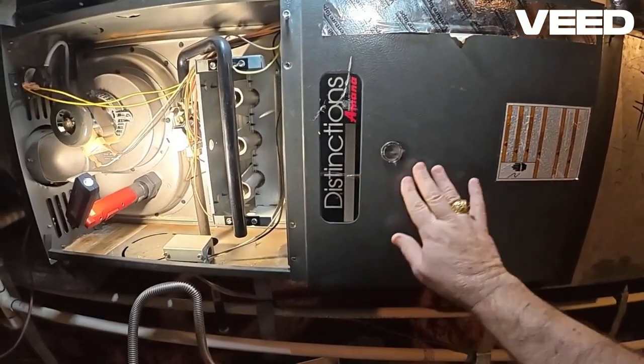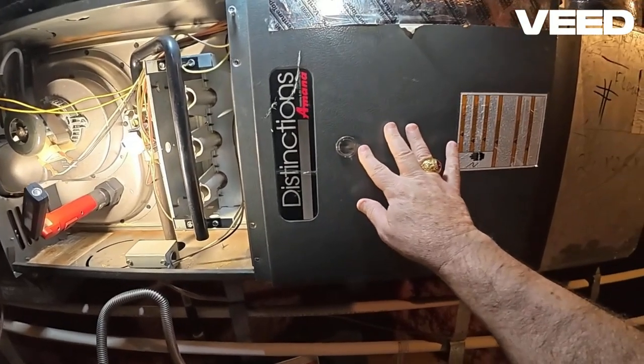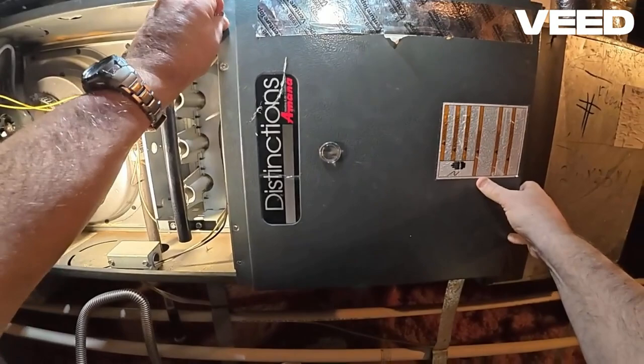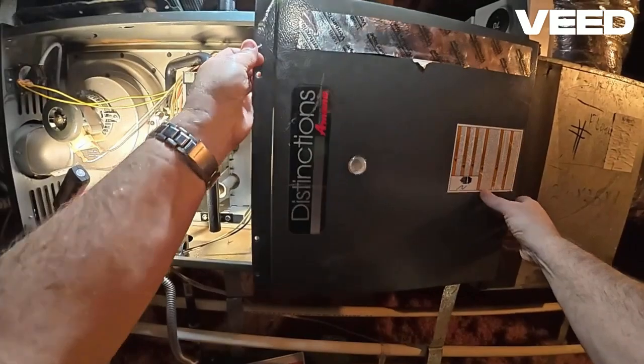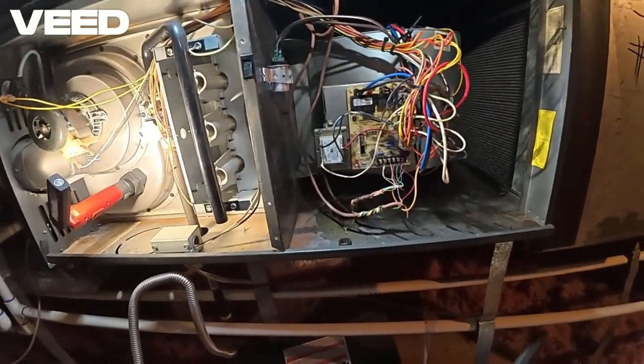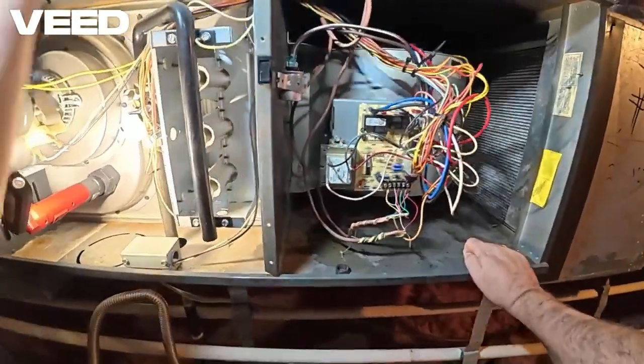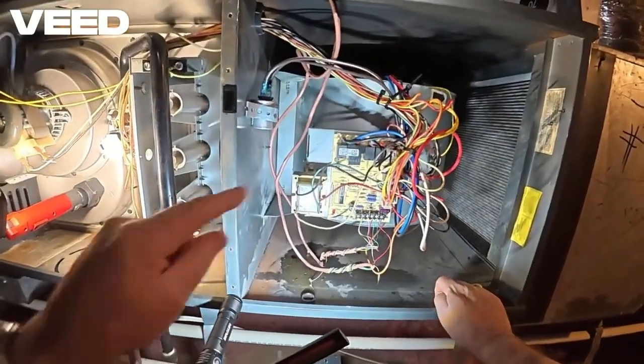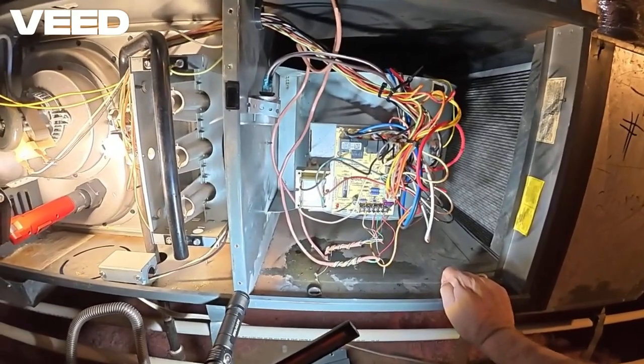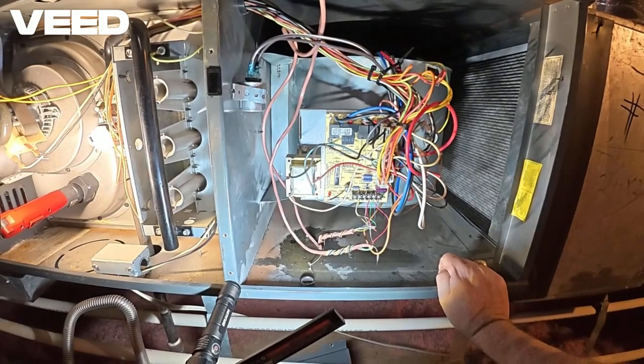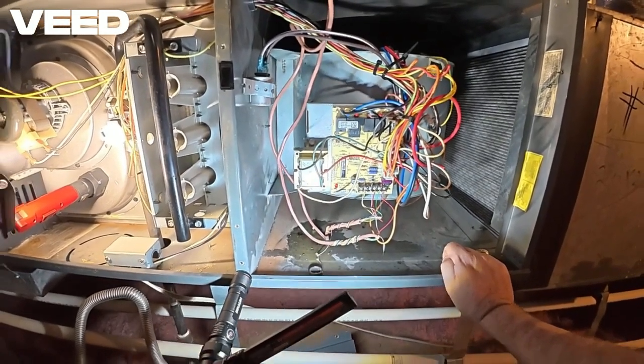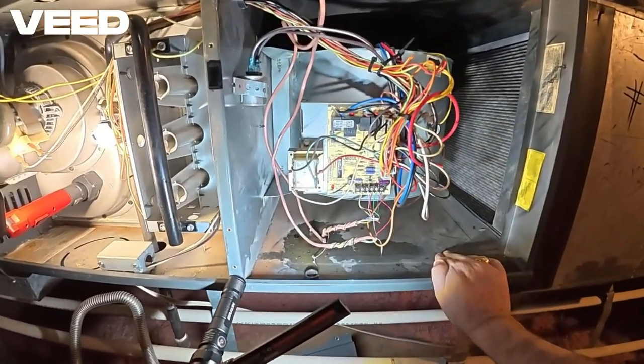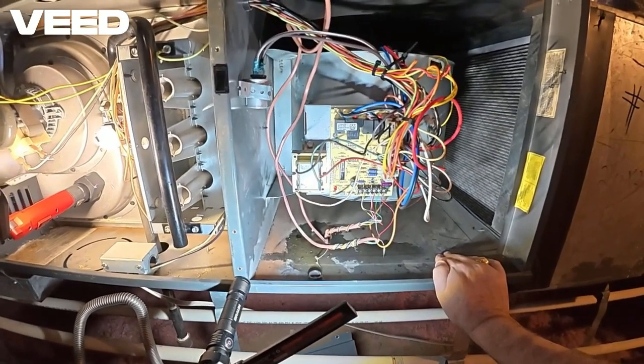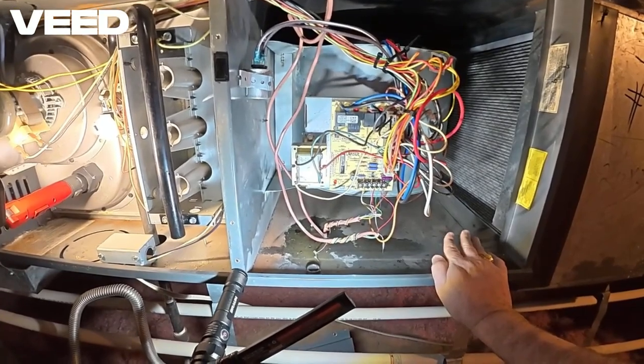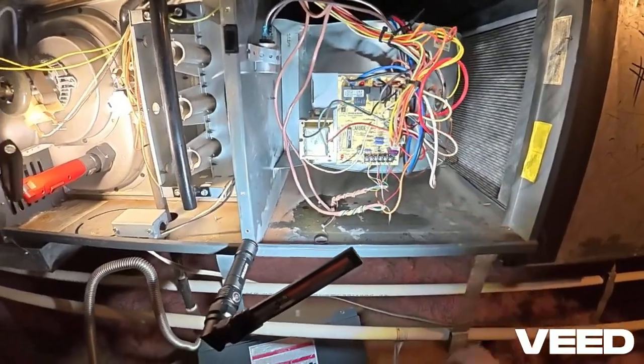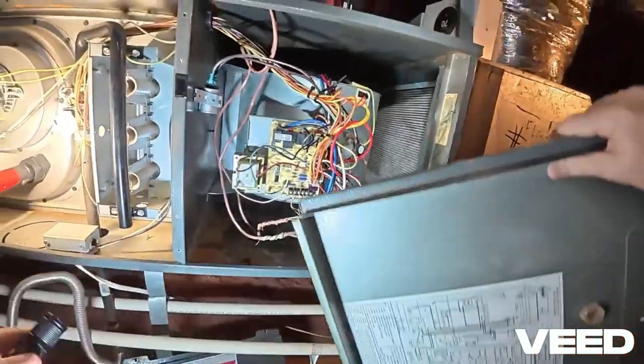So if we look on our panel, most have this type of a sight glass, let's call it, and it's plastic, and you can look in there and see the LEDs. In my case here, we have one LED and it's red. If you can, let me get some light on this down here at the bottom. So this is a red LED, and on other systems, there might be a red one and a green one, for example, and they flash in different sequences and speeds, and depending on the flash speed and sequence, it could point to potential issues. And I'm going to give you an example of that.